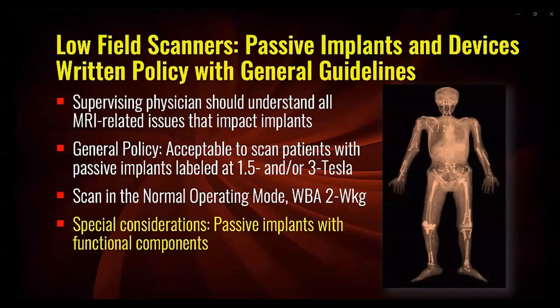This individual should have a complete understanding about the MRI-related issues that can impact a passive implant. Considering the effects of force, torque, and MRI-related heating, patients with virtually all passive implants that have been labeled at 1.5 and/or 3 Tesla can be safely scanned on MR systems operating below 1.5 Tesla. This includes scanners with horizontal or vertical fields, or another way to consider the direction of the static magnetic field is with reference to the field being longitudinal or transverse to the patient undergoing MR imaging.